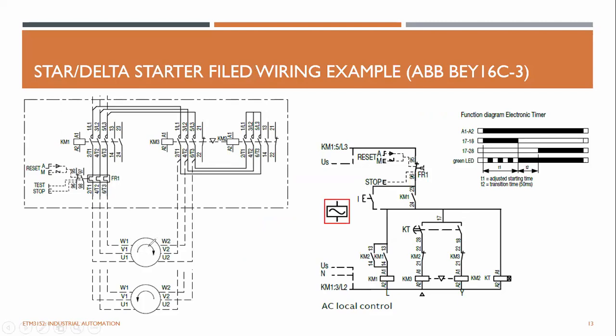Even though it is a star delta, someone has to wire it for one direction. You can't change the direction with this setup, right? So either you have this wiring, which runs the motor in this direction, and you can switch to star delta. If you wire in this way, the motor will rotate in the other direction, and you can do the star and delta connection. But you cannot change the directions with this ABB BEY16C series. It only allows changing star to delta for running in one direction only, right?